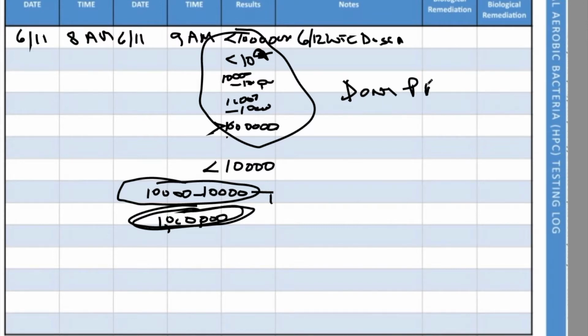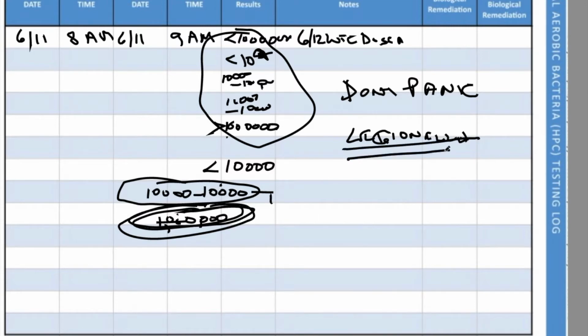One of the things about this microbiological test is it helps you understand whether you're feeding too much biocide or too little biocide, and calibrate it a little bit better. There's no strong evidence that a high bacteria level necessarily means a high Legionella level. The Legionella test is for a specific bacteria that may or may not be part of this. In many cases, you can have a high bacteria count and not have any Legionella present, or not have high levels of Legionella present. So don't let this scare you.